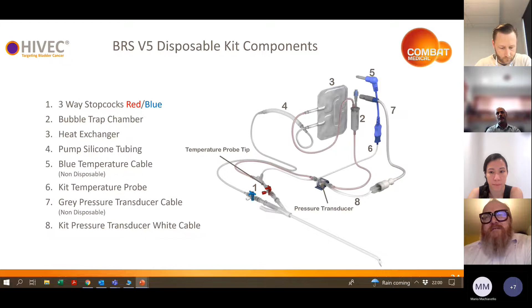The temperature will then drop when we add the chemotherapy because it's a bit colder. The temperature continues to rise, hits the red line, which is the set temperature. As soon as the fluid temp and the set temp are the same, the duration starts to tick down over here, and it travels along, on top of the red line because it's so accurate.